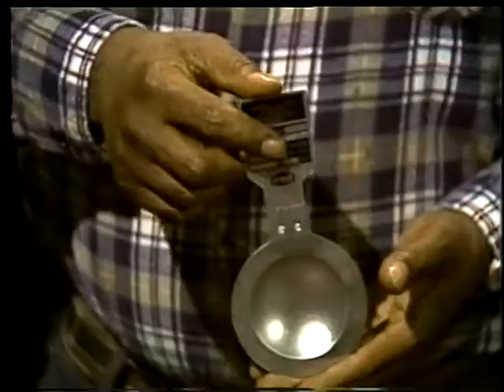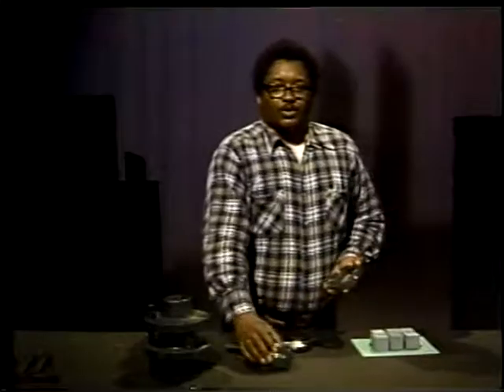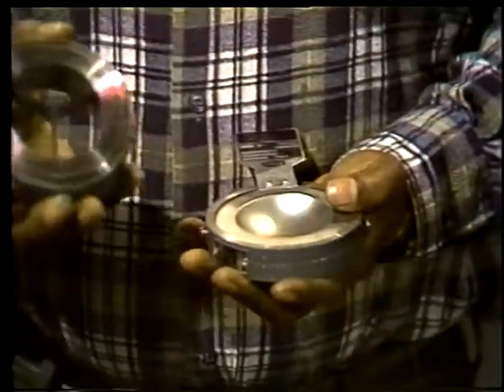This is another type of rupture disc called a reverse buckling disc. It consists of a disc and a frame with a sharp knife point. A reverse buckling disc is installed with the bulge extended into the system and the knife point on the outside. When pressure rises above what is normal for the system, it pushes the bulge outward. When the bulge meets the knife edge, it bursts, relieving the excess pressure.